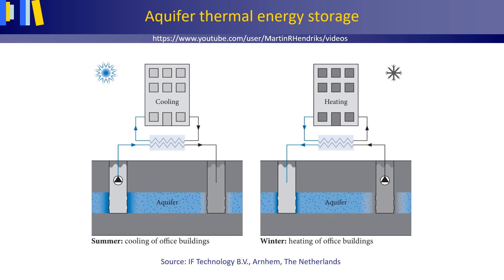This figure shows the principle of aquifer thermal energy storage. The left part of the figure shows the summer situation where cold groundwater is pumped out of an aquifer. The cold water is used for cooling a building using its air conditioning system via a heat exchanger.